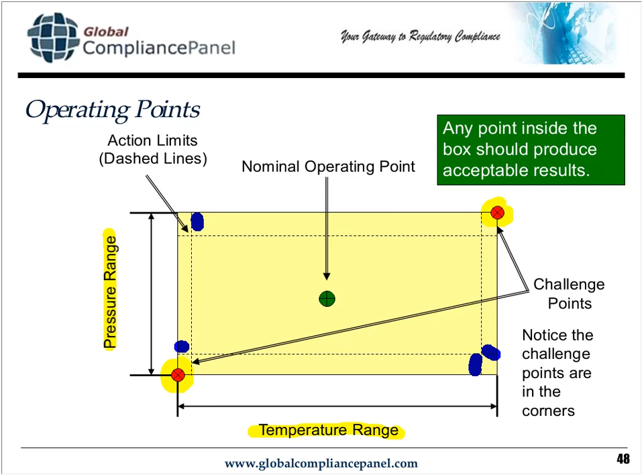So this is the idea of monitoring and controlling the process input parameters. I'm going to monitor them with a certain frequency, making sure they stay inside the box defined by the dashed lines. If they go outside the dashed lines, I'll readjust them to make sure they don't go outside the solid lines. That's how I'll set up my monitoring parameters, frequencies and intervals. I'm going to run the challenge points, make sure everything works correctly inside the solid box, and then set everything so that I actually operate inside the dashed lines box.